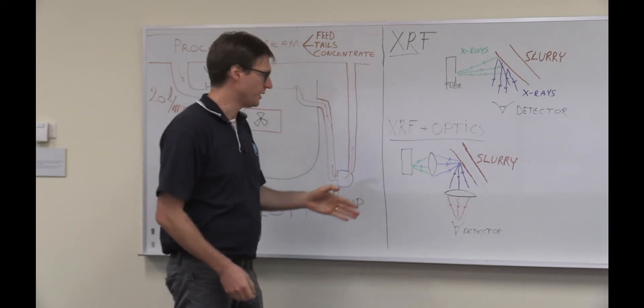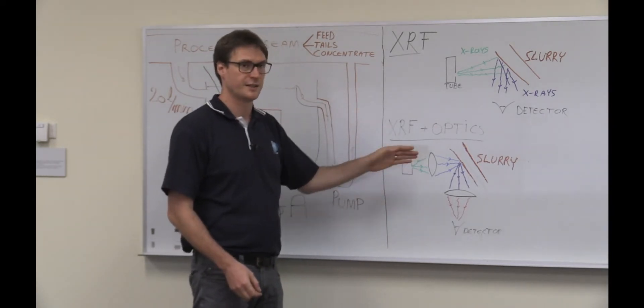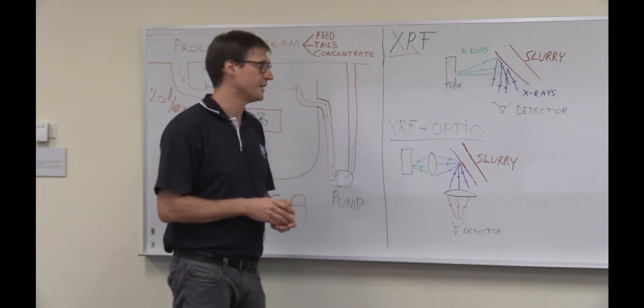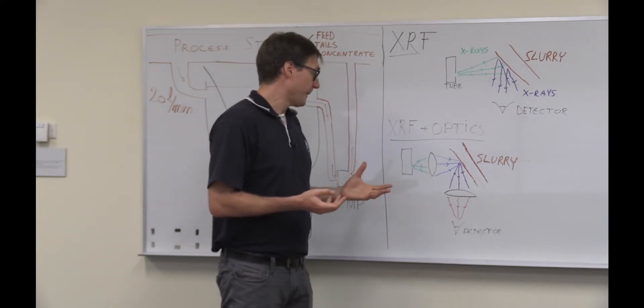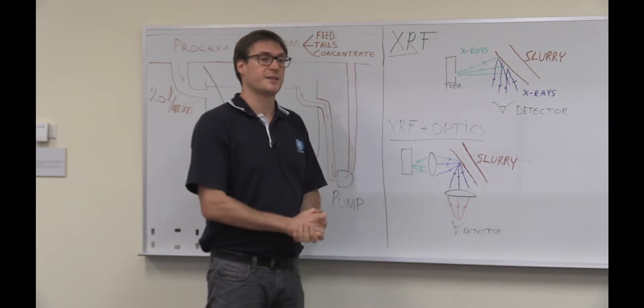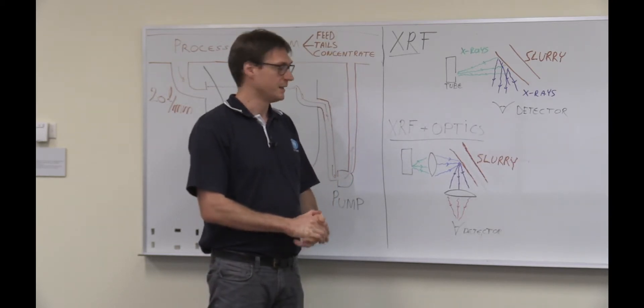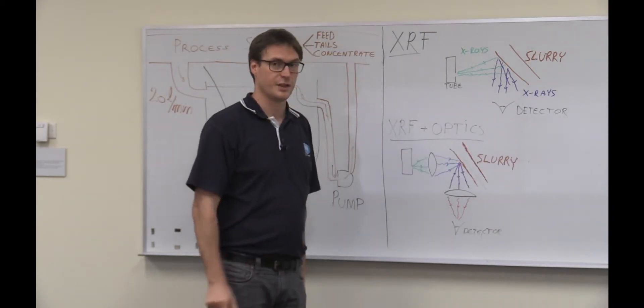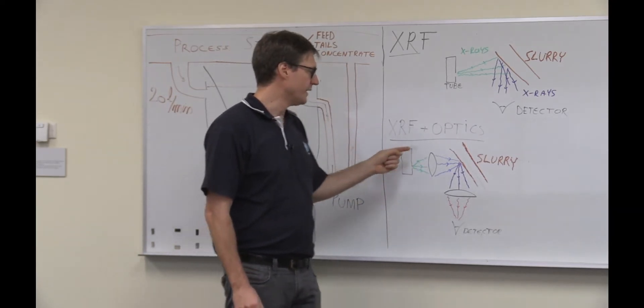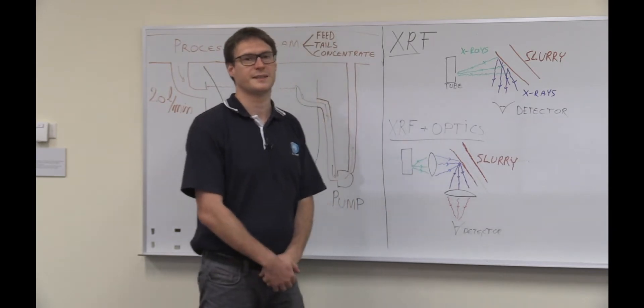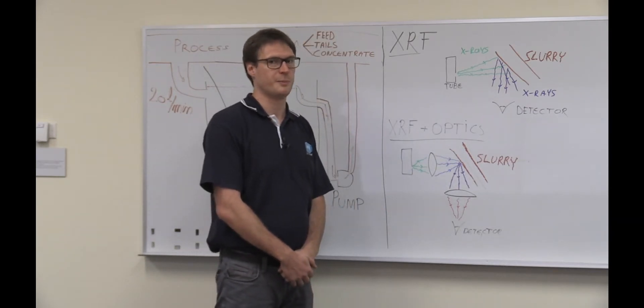So the setup is similar. You have an X-ray generator that generates X-rays at a lot of different energies, and then you have the first optic, which works as a lens. So it collects X-rays over a large solid angle and focuses them down to a point on the slurry. And at the same time, it only does this for one particular energy, and the X-ray energy we choose is the one that excites gold atoms the best.